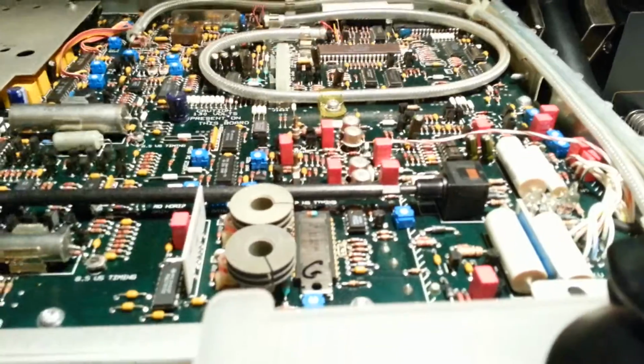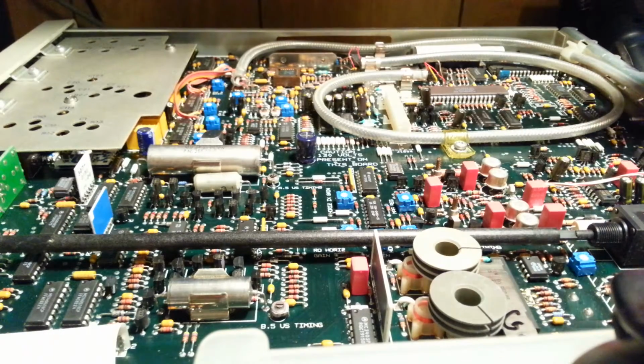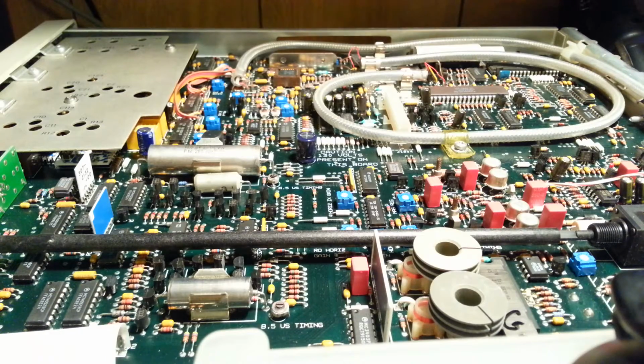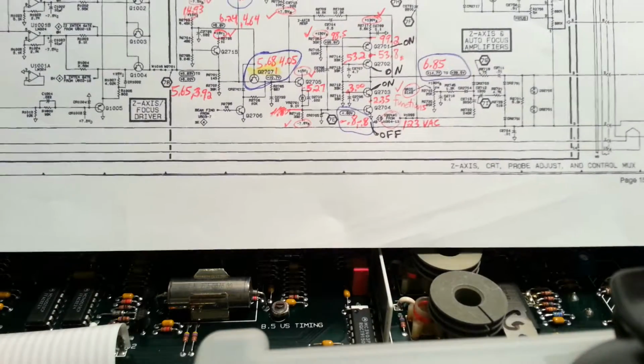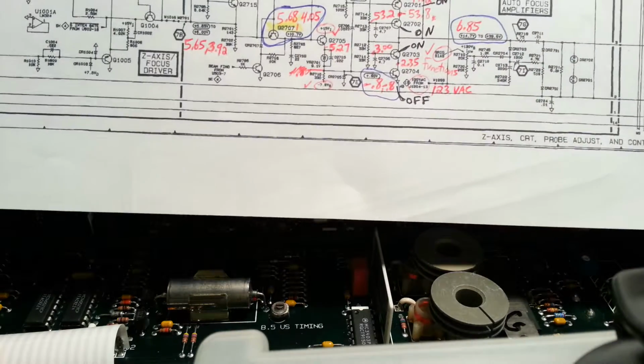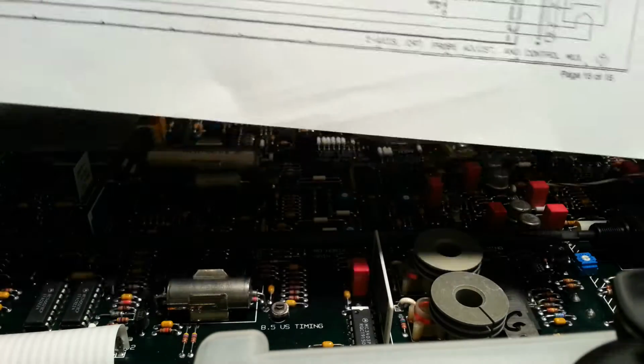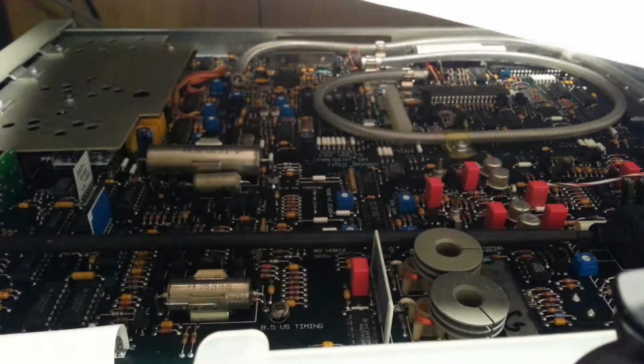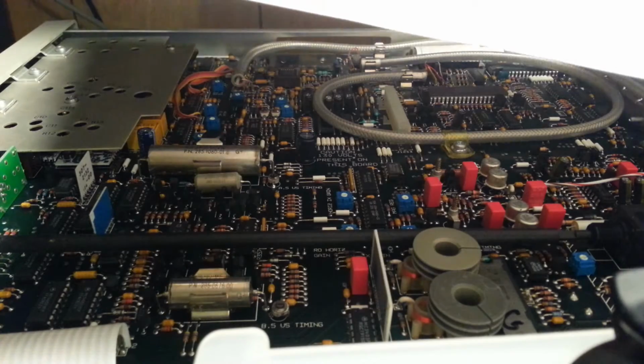Anyways, so I checked the voltages here at jumper 1204, and they all check out fine. You could look in the service manual. And so the next item is to pull up the schematics to see where exactly the problem is. The key schematic that we're going to look at is the Z-axis, CRT, probe adjust, etc. This is diagram 7 of the service manual, and this is very similar for the 2245 and the 2246 models.